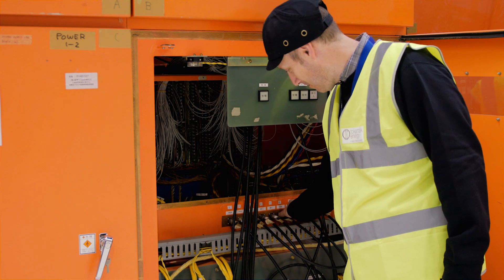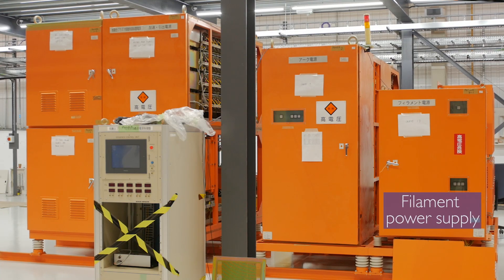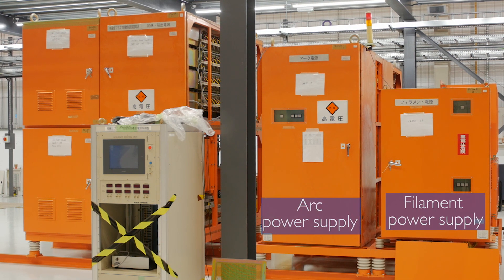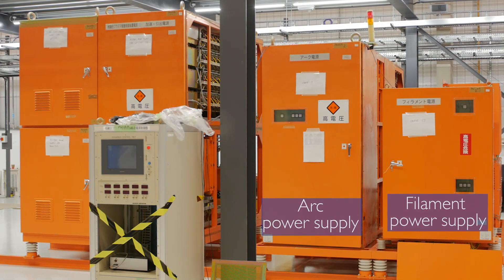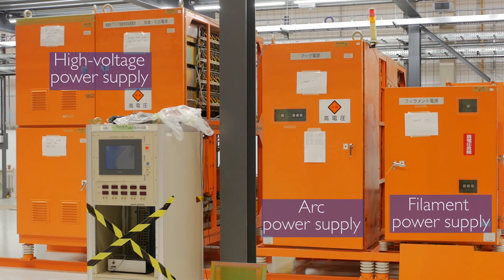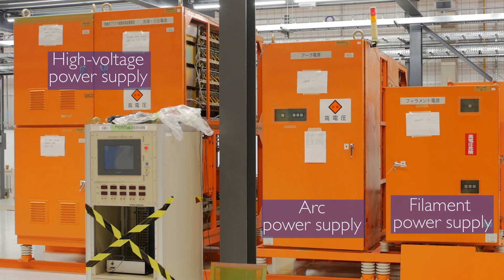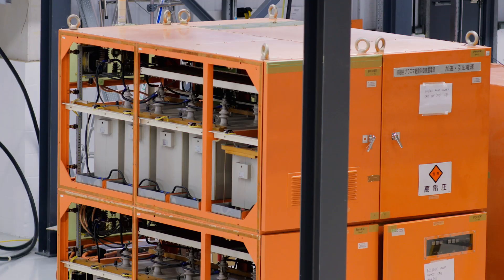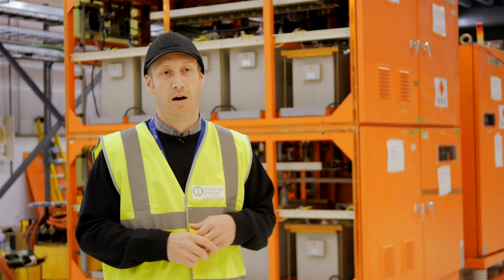We have three main power supplies. In the far distance we have a filament power supply which is thousands of amps of current. We have an arc power supply which is hundreds of volts and hundreds of amps of arc current to establish plasma. And we have a high voltage power supply which is in the order of 30 to 100 kilovolts high current which is there to generate high voltage to accelerate the ions.